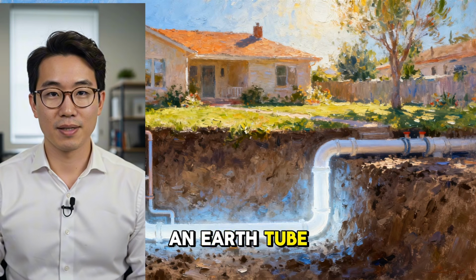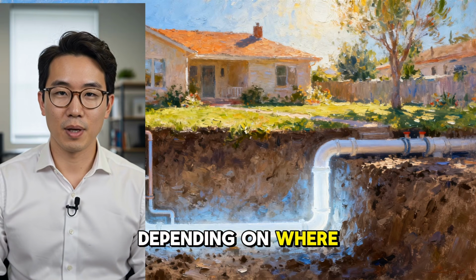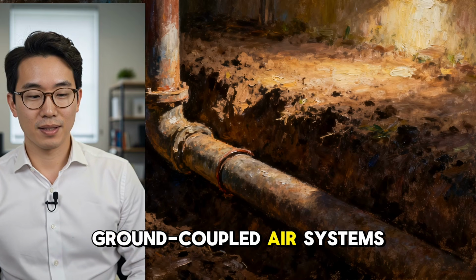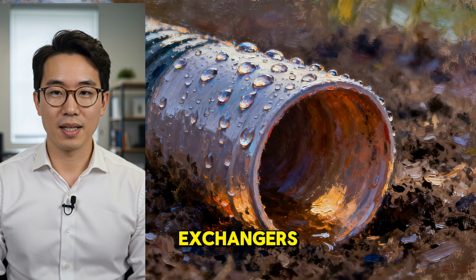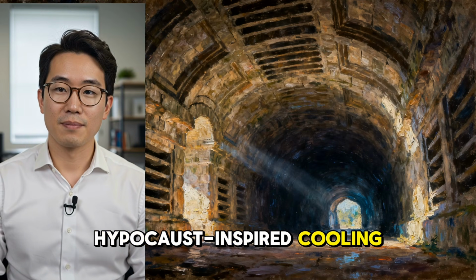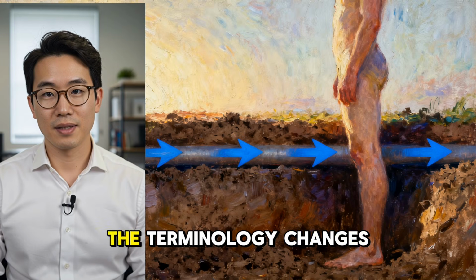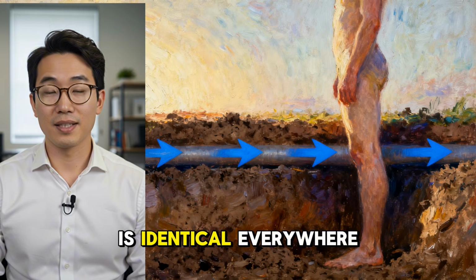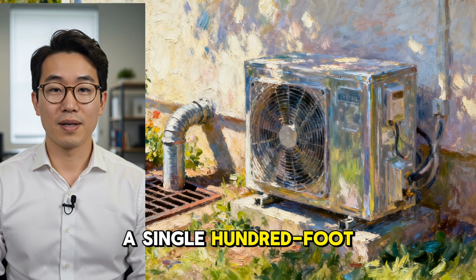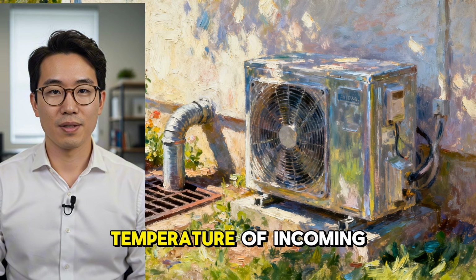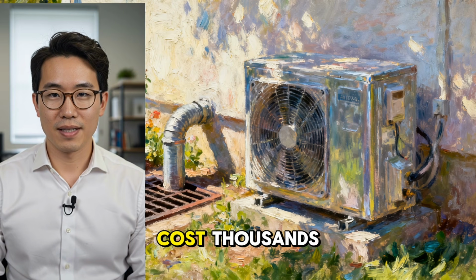This is called an earth tube system, and it goes by several names depending on where you encounter it. Ground-coupled air systems, earth-air heat exchangers, hypocaust-inspired cooling, underground ventilation channels. The terminology changes, but the physics is identical everywhere. A single 100-foot length of buried pipe can transform the temperature of incoming air in a way that would cost thousands of dollars to replicate with mechanical equipment.